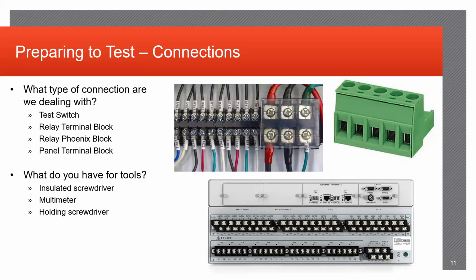The biggest thing you want to look out for is verifying polarity on the test switches themselves, so that you're injecting currents and voltages into the relay itself and not back out to the yard. This could cause a backfeed going back up into any high voltage equipment and cause very, very dangerous issues. So once you've identified that all your test connections going up to the relay are correct, make sure you have all the correct tools for the job: insulated screwdrivers and your meter. These are all important tools when testing, not just relays, but wiring checks and functional checks as well.